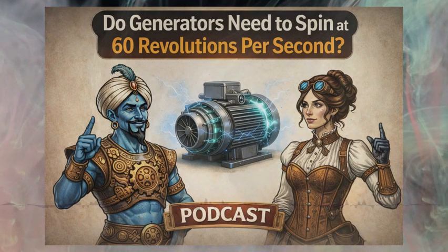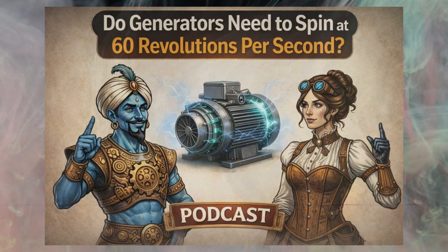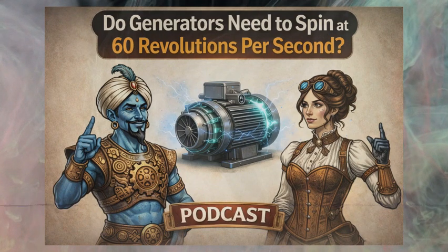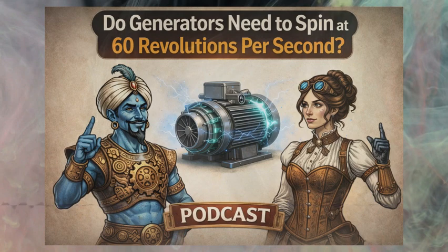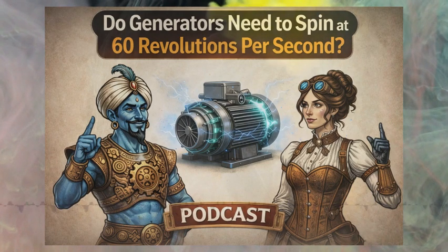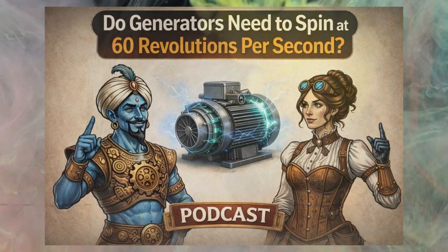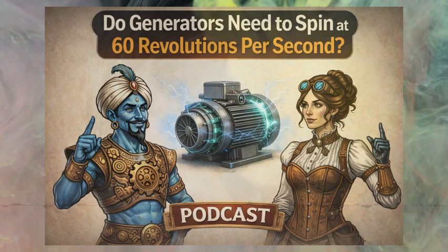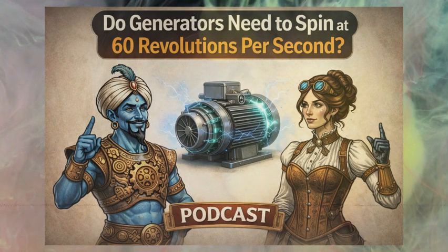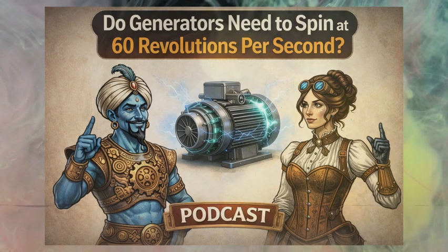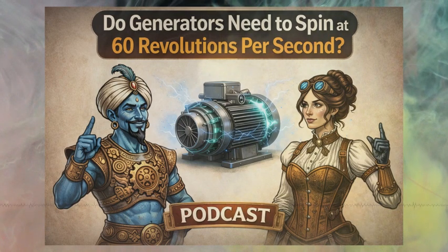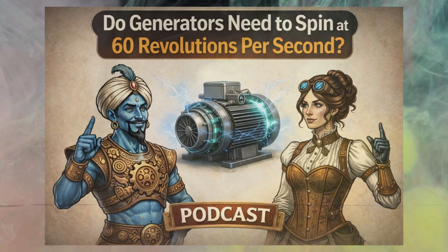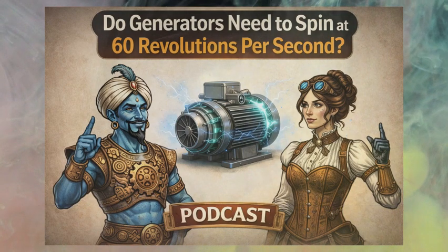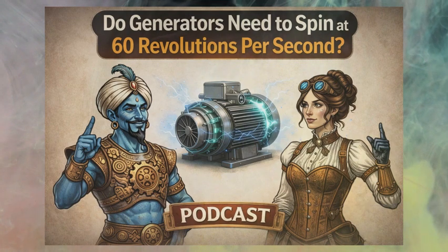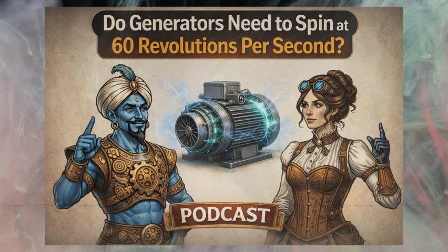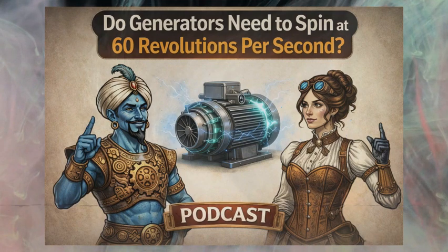And if we double it again to an 8-pole generator, speed is cut in half again, 900 RPM. And for some of the really big, slow hydro turbines, they might need something like, what, a 20-pole rotor? Exactly, and a 20-pole rotor would only need to spin at 360 RPM to produce perfect, grid-stable 60 hertz power. That is the answer. The slow-moving giant compensates for its lack of speed with sheer magnetic complexity. More poles, more cycles per turn. And that very requirement, the speed of the prime mover, ends up dictating the entire physical design of the rotor itself. It creates this clear divide in how you build these things.